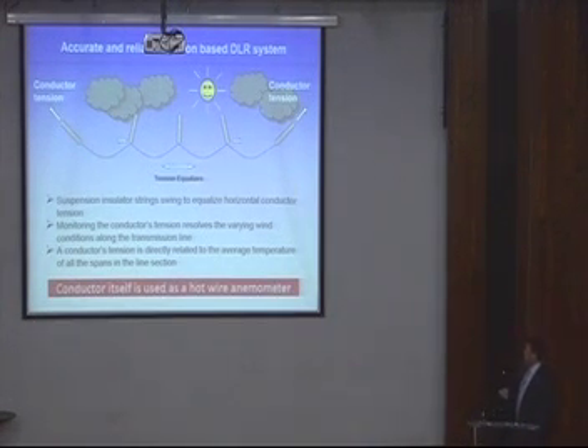So you can say what we are doing is using the conductor itself as the hot wire anemometer. The conductor temperature locally is exactly what impacts the tension, and the average of these local impacts results in a tension. It also has an impact on the inclination at a given point. Wherever you put this sensor measuring the inclination, it has the same possibility as the tension. With this change in inclination, you can identify the conductor temperature and the sag condition in that section.